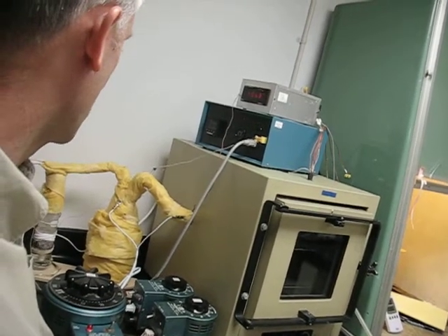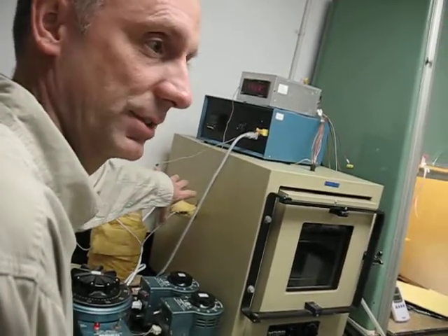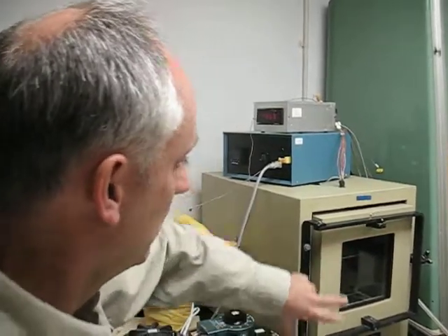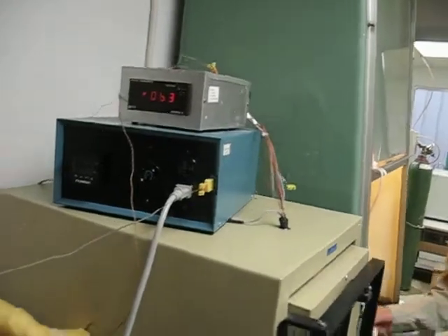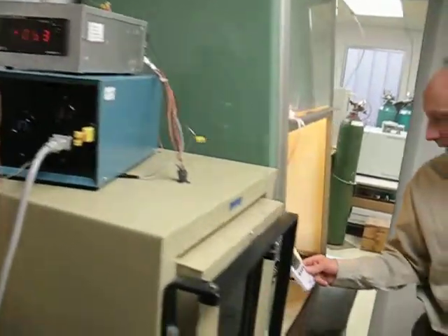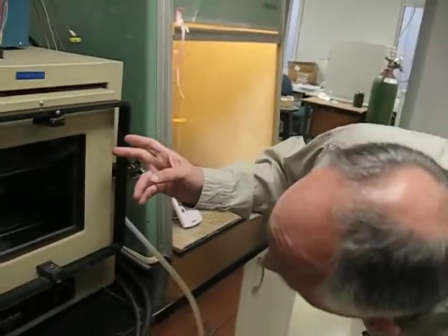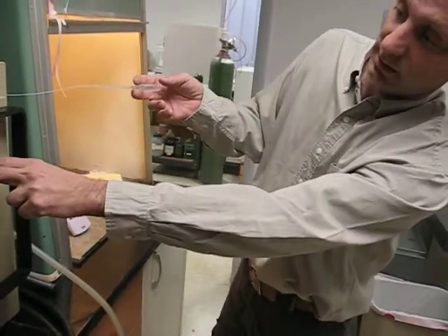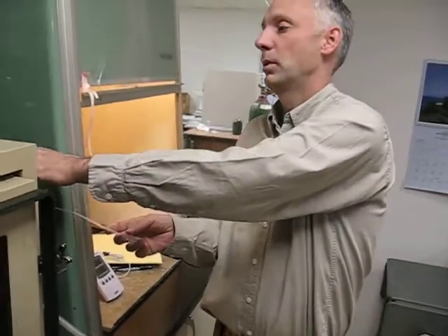That's not perfect for various reasons, whether it may be a little sub or super saturated from that value. We can monitor in here in 2 different ways. We have a relative humidity sensor, and we have what I believe is the more reliable wet bulb, dry bulb technique, whereas right in the wind field of this fan, we have a wet bulb and a dry bulb.